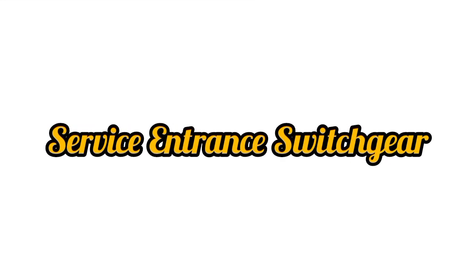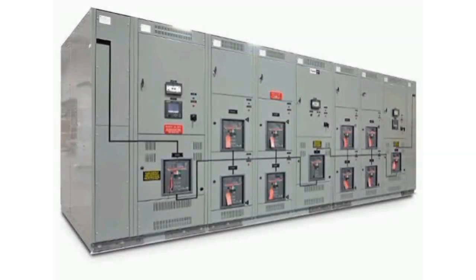Service entrance switchgear. When power arrives on site, it enters through service entrance switchgear. This is the first major piece of electrical infrastructure inside the facility. It receives incoming medium voltage utility power, provides main overcurrent protection, contains protective relays and metering, segments downstream distribution, and allows isolation for maintenance. This equipment establishes the facility's internal electrical control boundary. From here forward, the data center manages its own reliability.